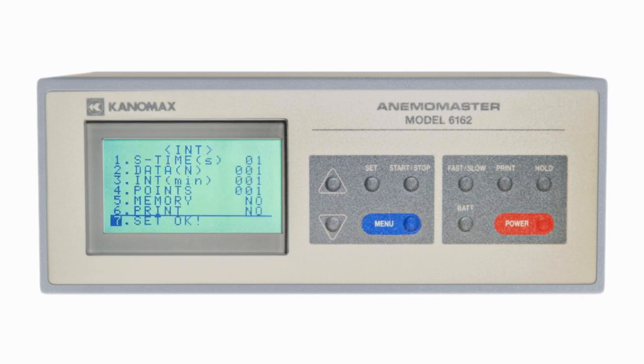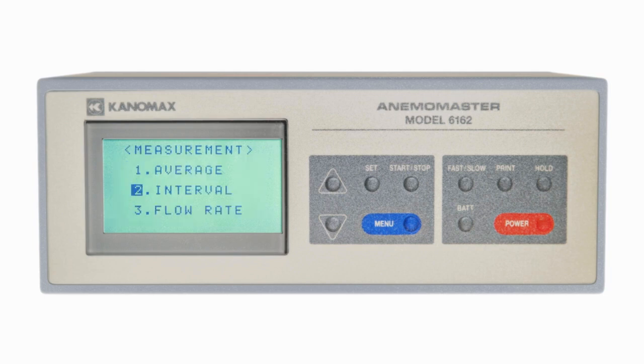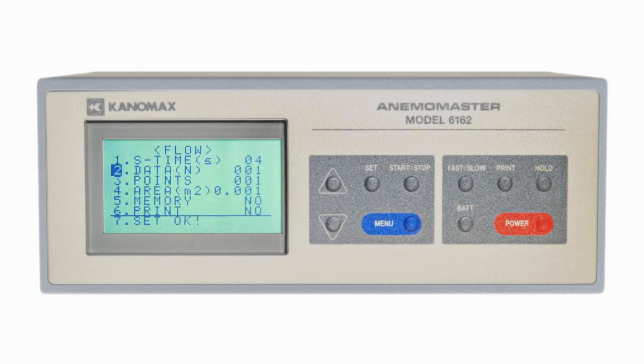Selecting interval in the measurement menu shows you some similar options, but now you have INT, which represents how many minutes it takes for the next sample to be taken, and points designates how many sampling sequences occur. Flow rate mode adds on to the options found in interval mode by including area, which represents the cross-section area of the duct you're testing. And although points may seem to be the same as interval mode, it actually defines how many points within the duct's area are being measured to obtain the average air velocity.